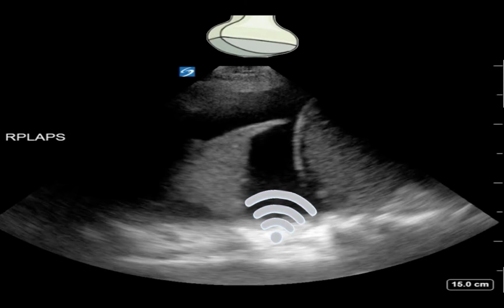deeper. The machine knows where to place each pixel on the x-axis based on which part of the probe's head they return to. It knows where each pixel is on the y or depth axis based on the time it takes for the echo to leave the probe, be reflected by a tissue, and then return to the probe. Echoes that are reflected by deeper tissues take longer to return, and so are placed deeper on the screen by the ultrasound machine.